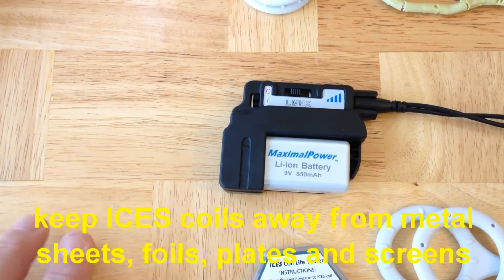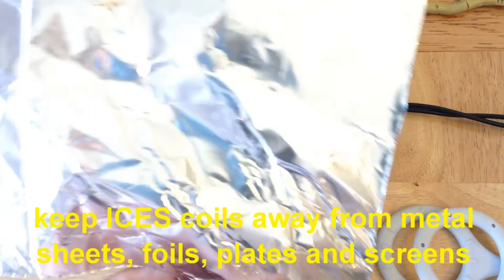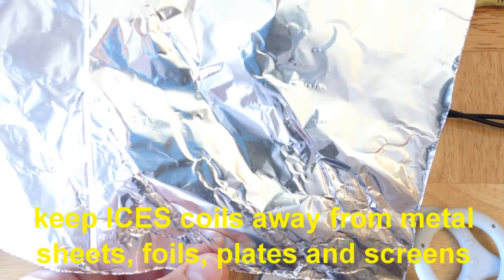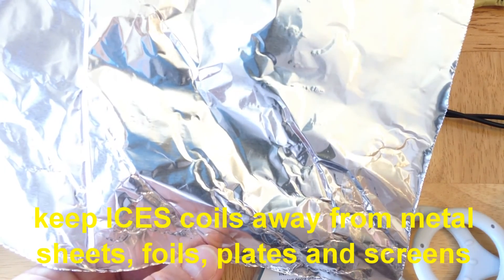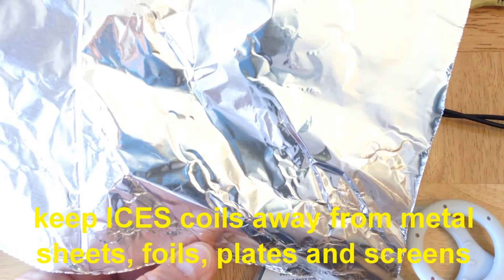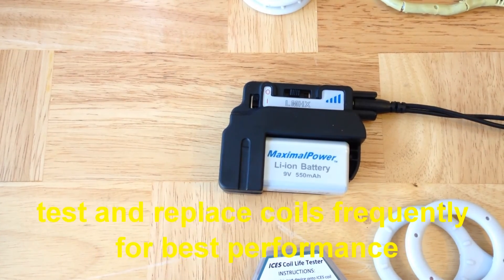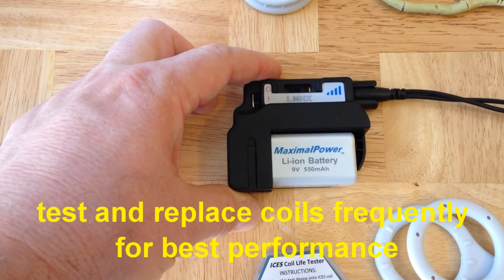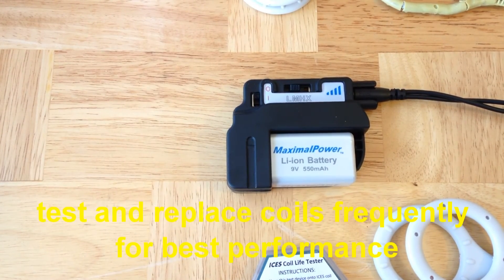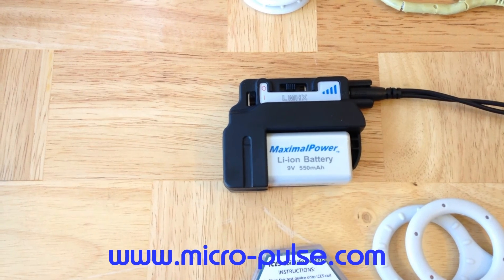A final thing to remember: keep your ICES system away from metal plates and screens while in use. This includes large metal sheets, plates, foils, coils, and screens, because metal surfaces like that can short the magnetic field while the system is operating. If you do these simple things, your ICES system pulse generator should last a very long time, and if you frequently replace the coils, your system will perform very well for a very long time.